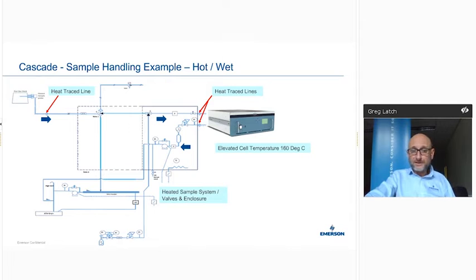It's actually a heated trace line, so not dissimilar to the traditional hot wet system. Then going through into your sample handling system panel. Our sample handling system panel in this particular case is actually running at an elevated temperature as opposed to cool, which happens in a lot of the cases as well. So in this particular case, we're actually running this cabinet normally at around 160 degrees C.